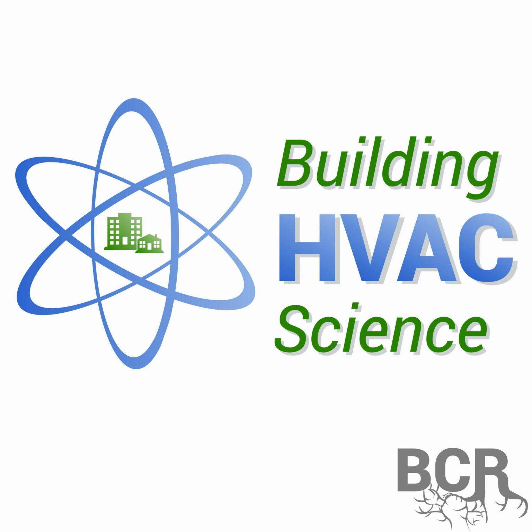To use the simplest formula, a key assumption is that the air is at a standard density. The conditions for standard air density are 68 degrees Fahrenheit, 0% relative humidity, and sea level altitude. That yields an air density of 0.075 pounds per cubic foot. I'm a real stickler. I put that 0 in front of the decimal every time. Just ask Jim Bergman. I used to annoy him with that constantly.